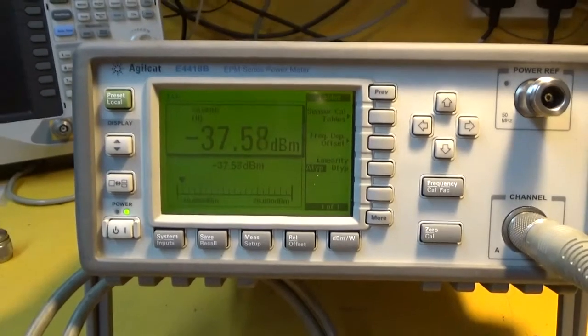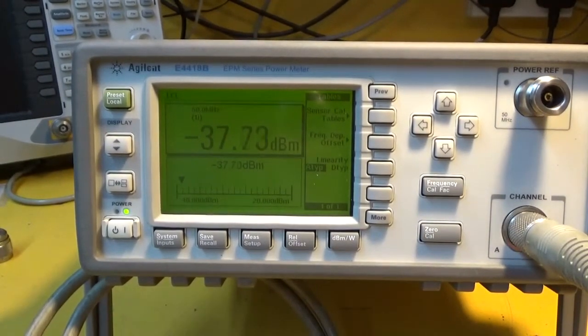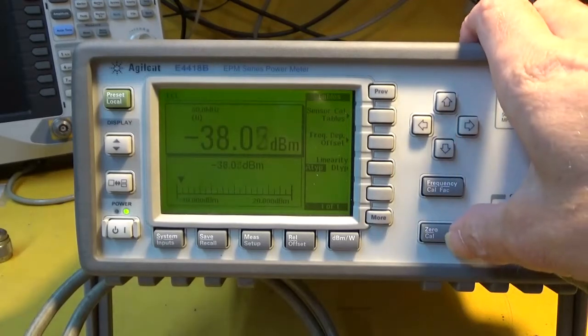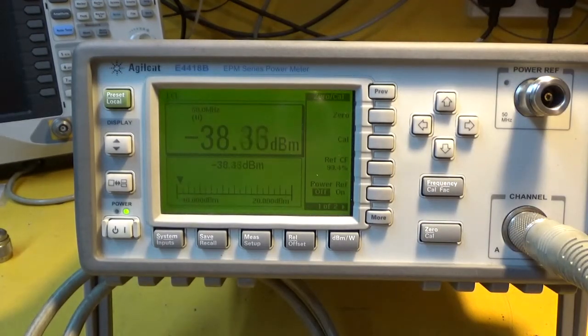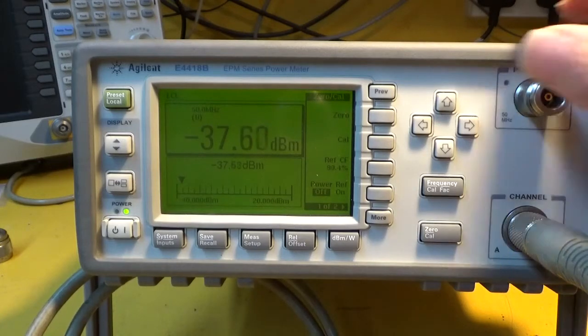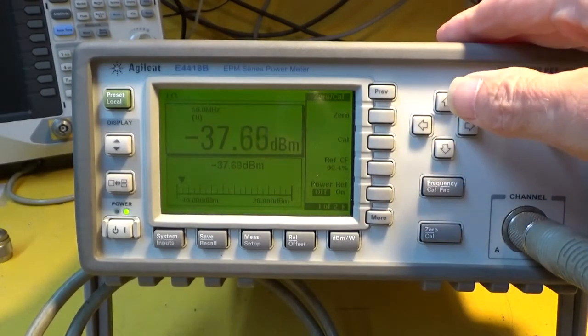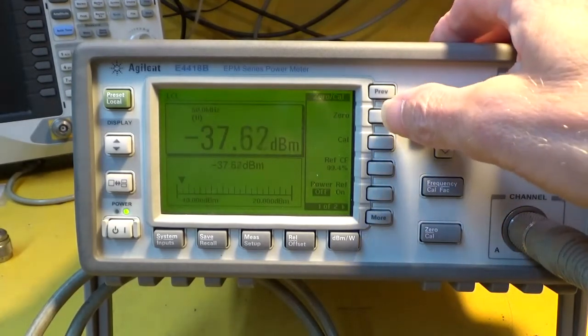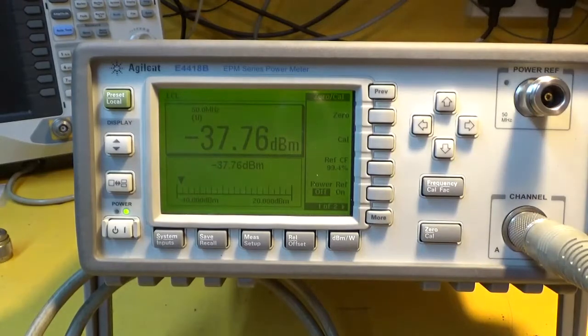So what you have to do now, once you've got your sensor connected, you first of all press 0 cal, and ideally you'd have this unit on for at least half an hour before you do any of the calibration, because you want it to warm up and stabilize. So first of all, you don't input a signal into the sensor, disconnect the sensor, and then you press 0. So now it's zeroing out the sensor. Takes a few seconds, not long. And it's coming out of the noise floor of the sensor.